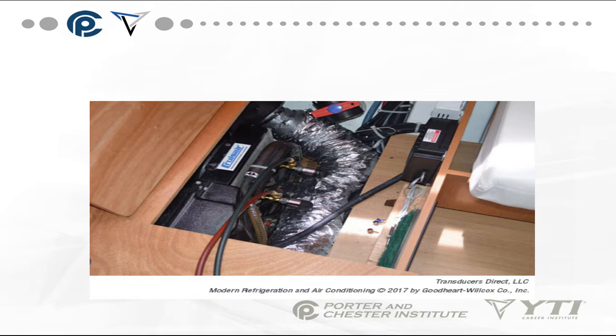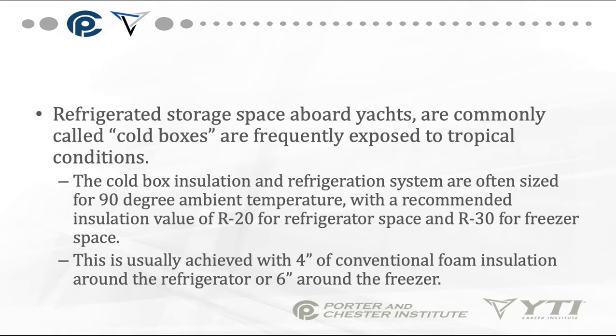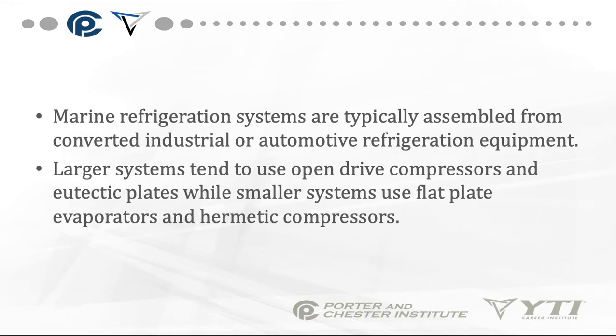The condenser must be easily cooled in the marine environment. Refrigerated storage spaces aboard yachts are commonly called cold boxes and are frequently exposed to tropical conditions. Cold box insulation and refrigeration systems are often sized for 90-degree ambient temperature, with a recommended insulation value of R20 for refrigerator space and R30 for freezer space — typically achieved with 4 inches of foam insulation for a refrigerator or 6 inches for a freezer. Marine systems are generally assembled from converted industrial or automotive equipment, with larger systems using open-drive compressors with eutectic plates and smaller systems using flat plate evaporators and hermetic compressors.